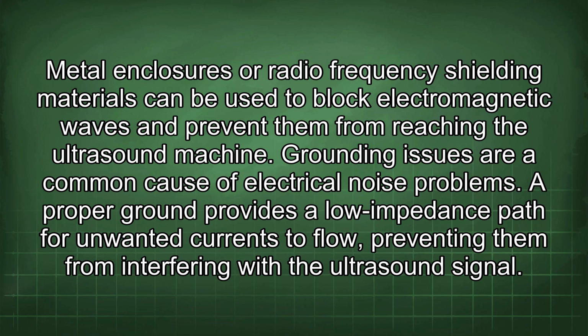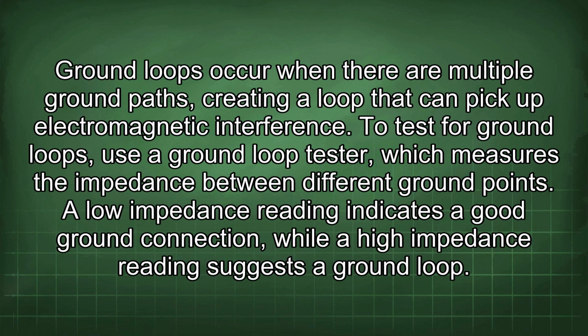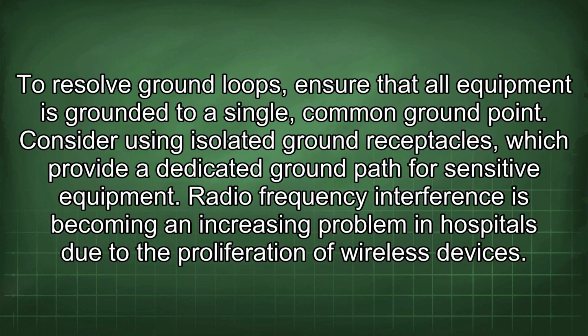Grounding issues are a common cause of electrical noise problems. A proper ground provides a low impedance path for unwanted currents to flow, preventing them from interfering with the ultrasound signal. Ground loops occur when there are multiple ground paths, creating a loop that can pick up electromagnetic interference. To test for ground loops, use a ground loop tester, which measures the impedance between different ground points. A lower impedance reading indicates a good ground connection, while a high impedance reading suggests a ground loop. To resolve ground loops, ensure that all equipment is grounded to a single, common ground point. Consider using isolated ground receptacles, which provide a dedicated ground path for sensitive equipment.